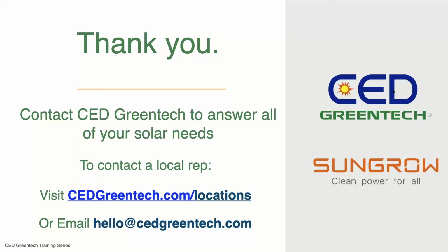Does the inverter have pre-commissioning capability to go through setup without the grid? Yes, definitely. That question's from Ben Frank. All we need is DC. All of our string inverters have dual power supplies, so whether it's connected to DC or AC, we're able to do all of the commissioning activities.